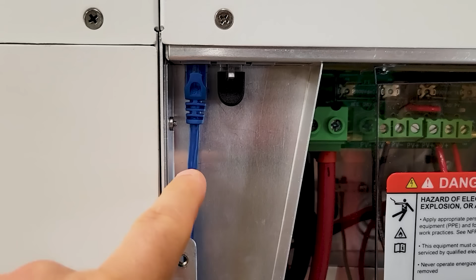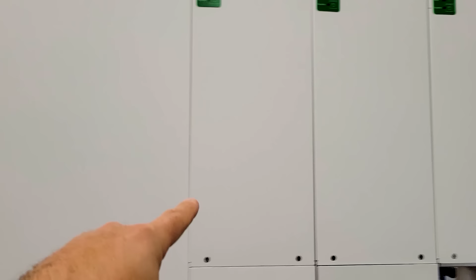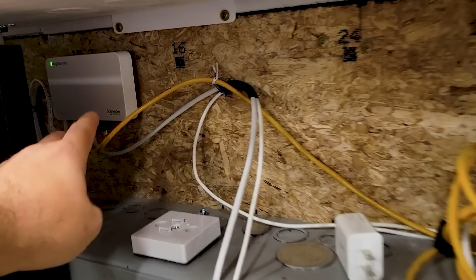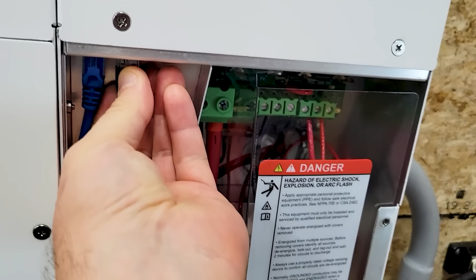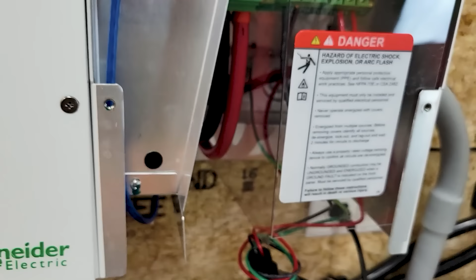The XanBus port has a termination on the end of it. This blue wire jumps to this charge controller, then over to this one, then to the second inverter, and down to the Insight Home. The Insight Home, which is this box right here, is self-terminated. So all we need to do is remove this termination end, and then we'll run a new Cat 5 cable from here over to the Link 2.